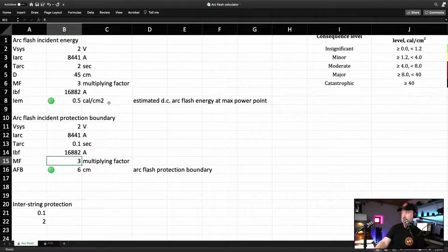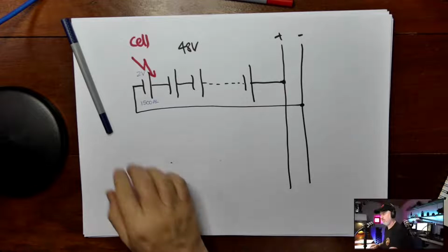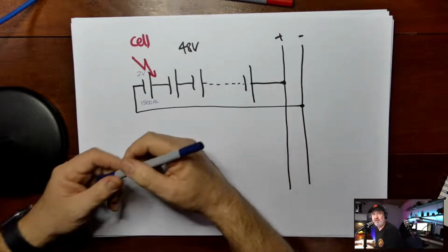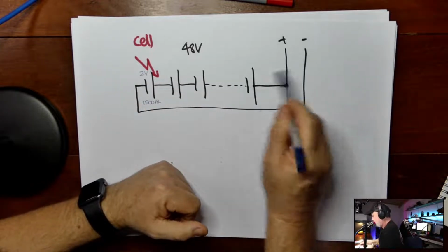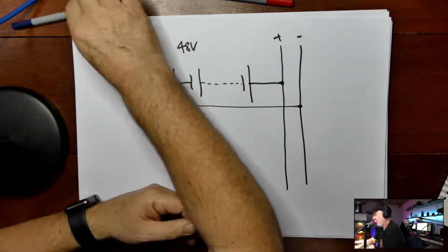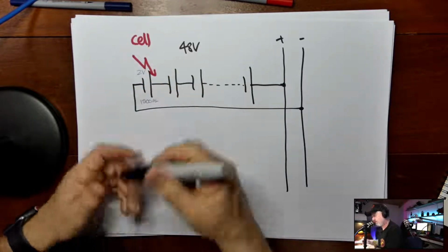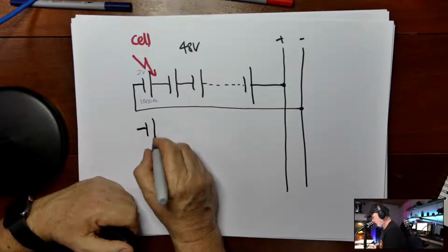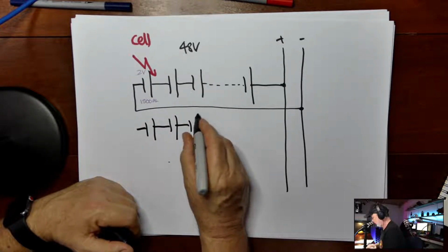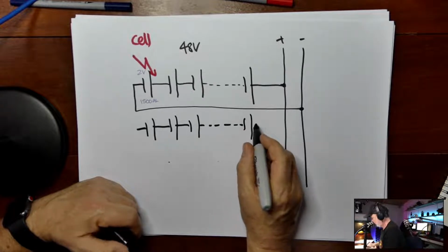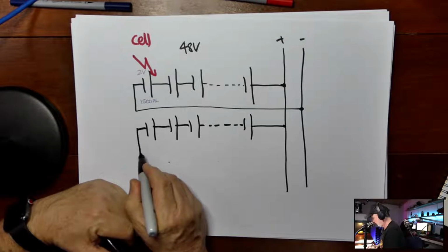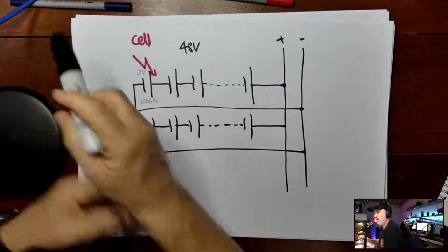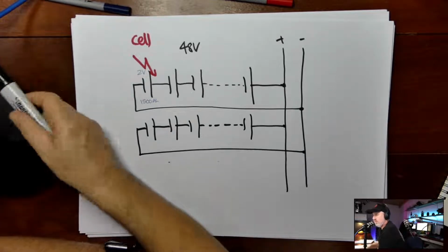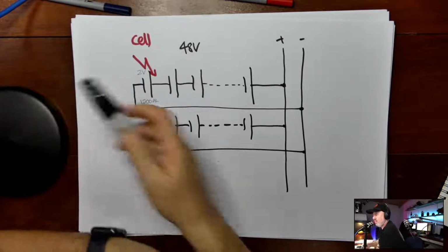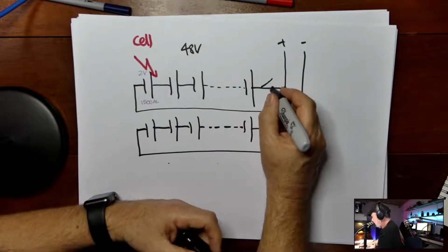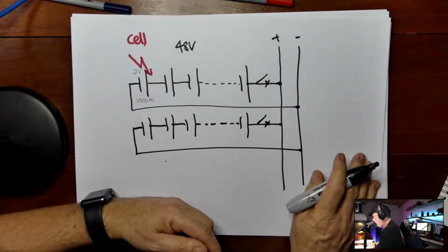Let's jump back to my drawing. So over here we're now going to look at another point in the system. Now we've wired up all the cells together, and at this point, we're now going to add another string of cells. So we have 2 strings, and as a result, with having 2 strings, we're now required to have string overcurrent protection. So I'll draw that in here. So we've got our string overcurrent protection on those 2 strings.